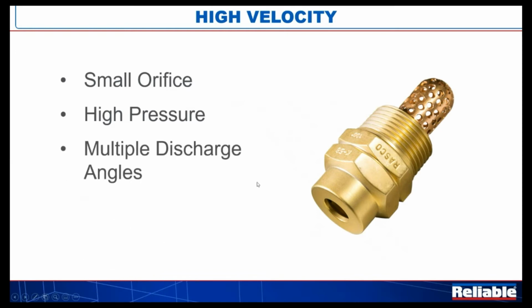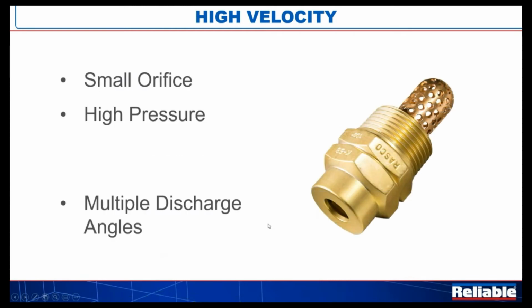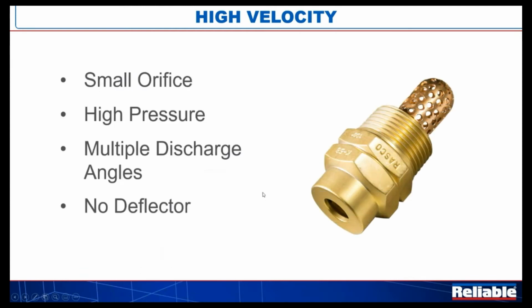Again, multiple discharge angles, the shape of the cone. In this case, you can't really tell from the end, the lower left end there, but interior there's a taper to it, and as that water exits, it's going to be a narrow cone or wider. So multiple discharge angles, and no deflector. The water is simply going to exit through, and it's going to come through in pretty large water drops. We again have no deflector to break it up.